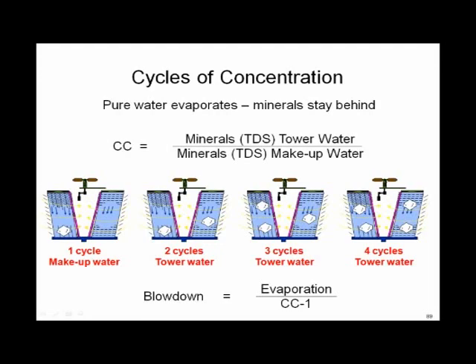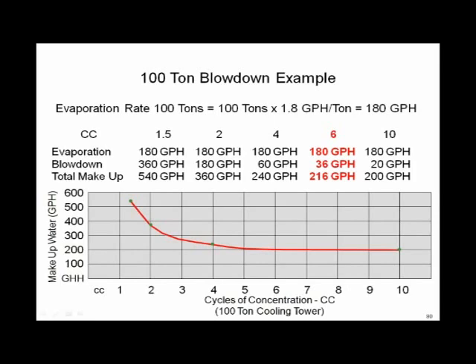As you can see, if you don't have some extra makeup water, you're going to wind up with a tower full of rocks. Sooner or later, you just can't keep going. So we've got to learn to deal with cycles of concentration. Here's a quickie chart to make the point. This is basically a 100-ton blowdown example of evaporation and blowdown and total makeup water required to a tower, based on the cycles of concentration.